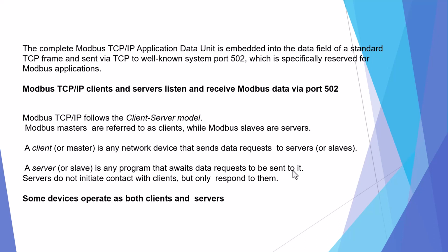If we use Modbus TCP/IP, we should know its port is 502. If you use some software and do Modbus programming, to listen and receive, just use port 502. Modbus TCP/IP clients and servers listen and receive Modbus data via port 502.